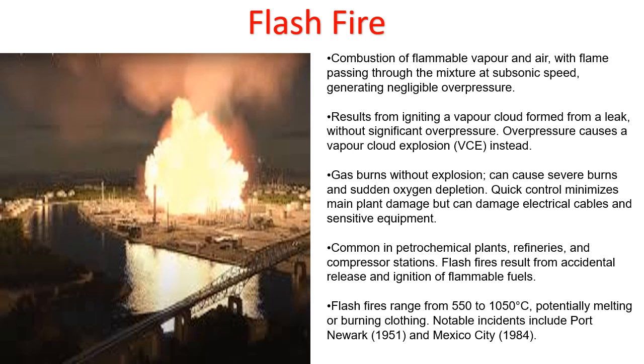Now, flash fire. Picture a room filled with flammable vapours — if someone lights a match, the entire room could burst into flames almost instantaneously. This is what happens in a flash fire. Flash fire occurs when a cloud of flammable vapour mixes with air and ignites. Unlike a jet fire, a flash fire does not create a significant overpressure situation. The fire burns with a rapid flame and causes severe burns and rapid oxygen depletion. This is the key difference between flash fire and vapour cloud explosion: in a vapour cloud explosion there is overpressure and an explosion, but in a flash fire there is no explosion — only fire.